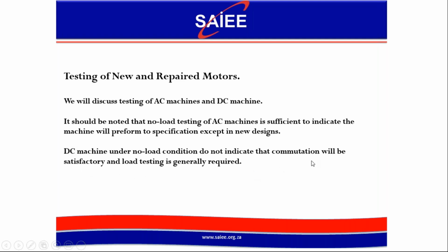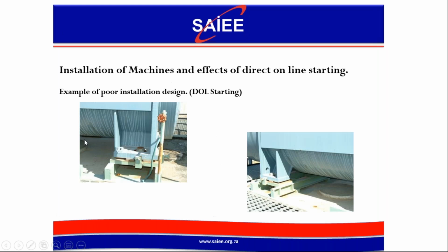DC machines are more critical, because no load conditions do not indicate anything about the commutation on the machine, whether the interpoles are correct, or whether the compensating windings are correct. Generally DC machines would require some load testing of some kind, a back-to-back type of testing, which works very well if you have two machines. So that will be discussed in the papers itself.